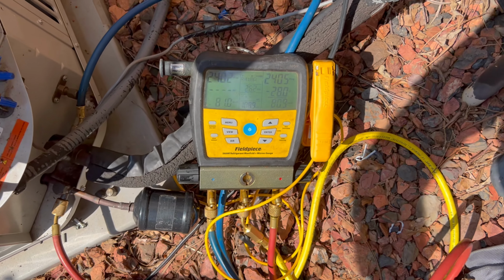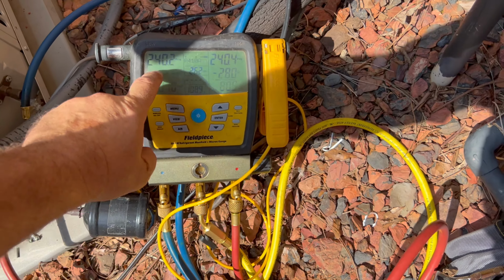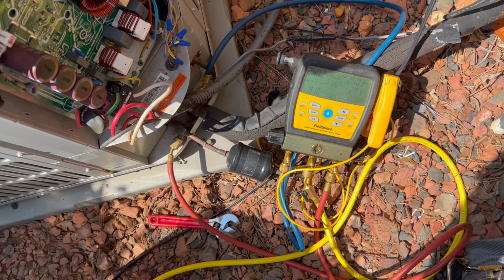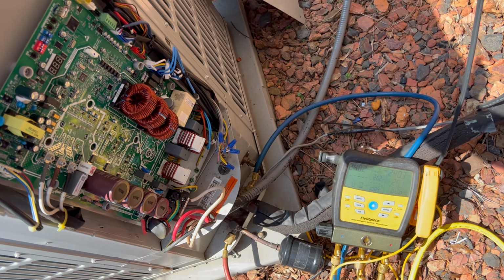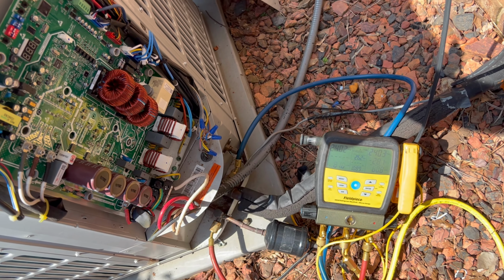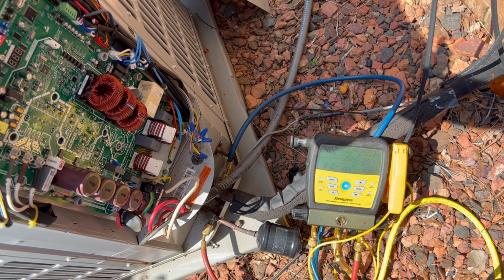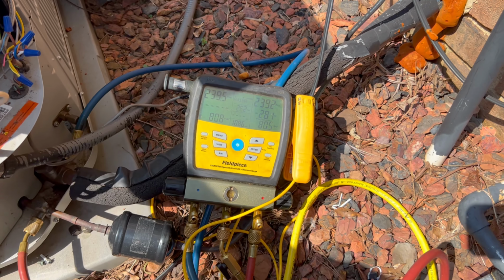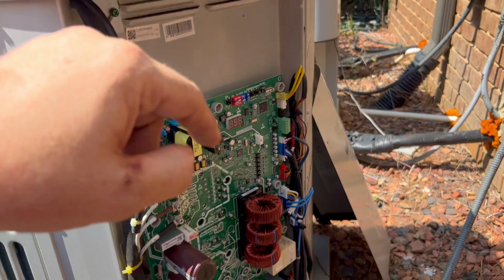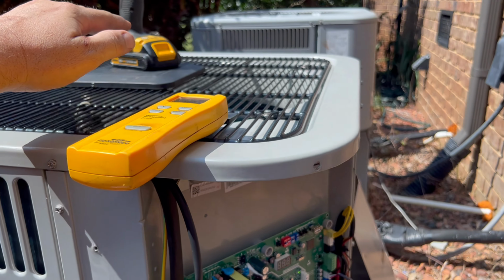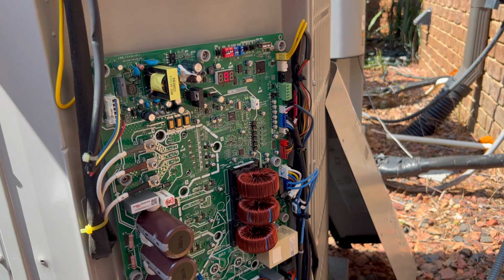We've stopped ambiently pulling in refrigerant, about 240 pound static charge. So we'll go ahead and plug this guy in, let him boot up and start up, and we'll show you how to put it in charging mode to ensure we have a correct charge. So notice our compressor's not running yet, but our condenser fan started. We just heard it click.